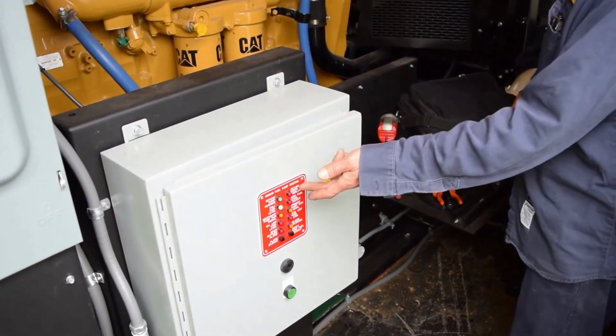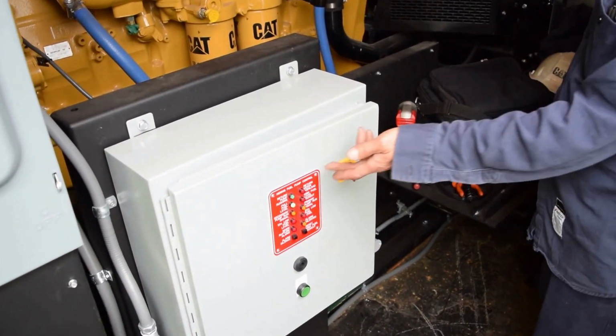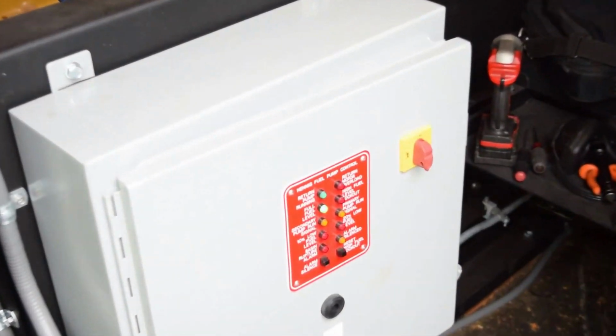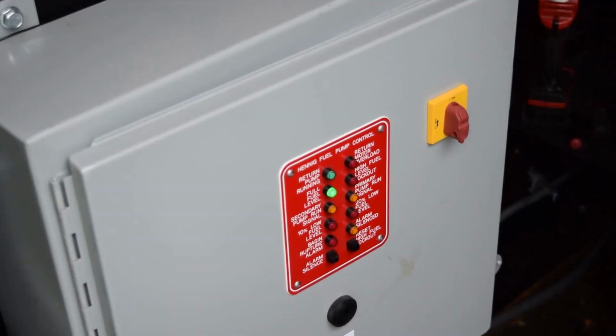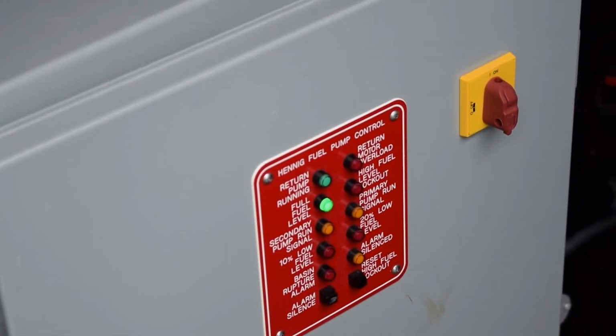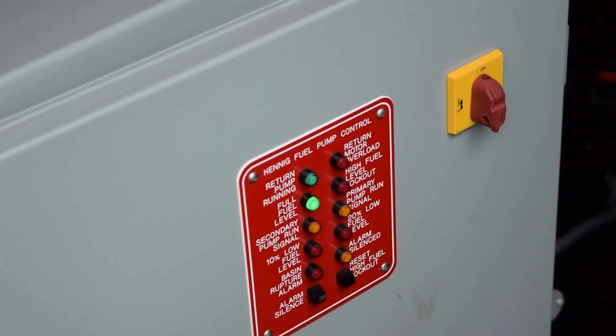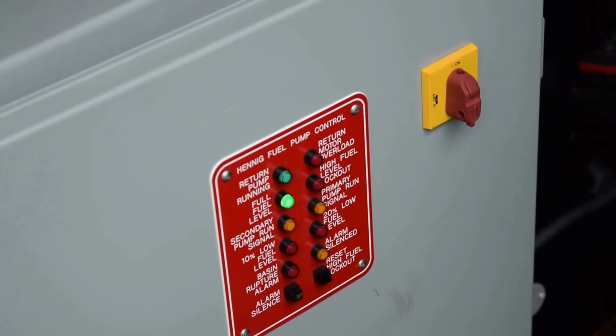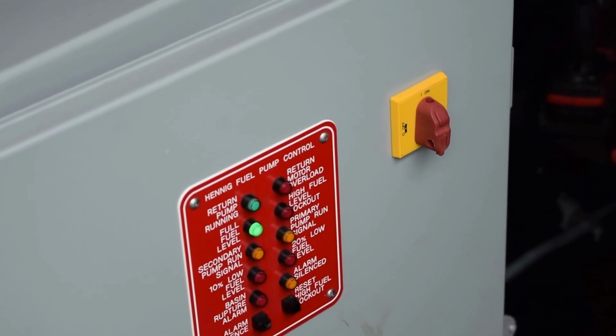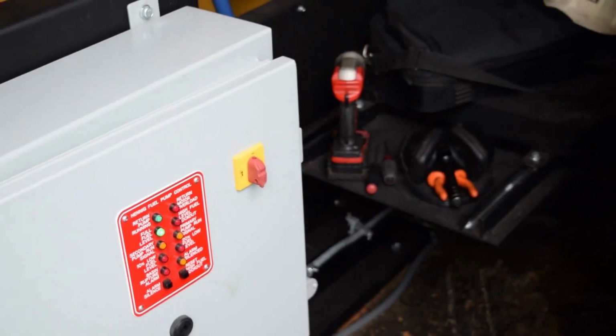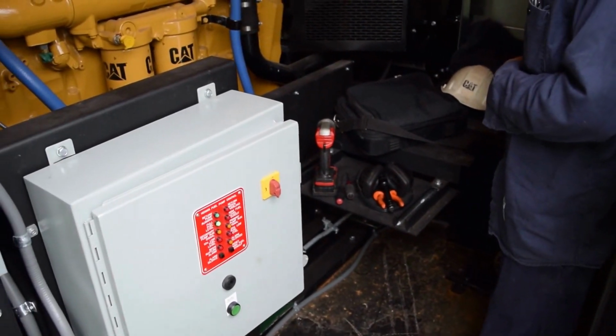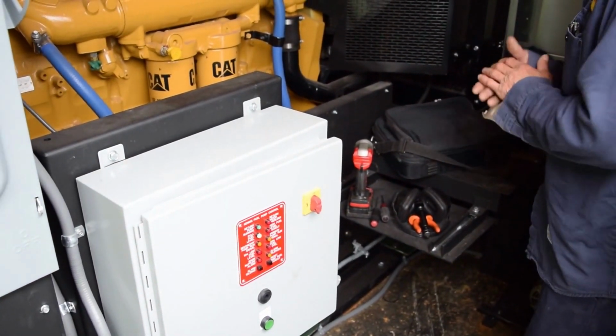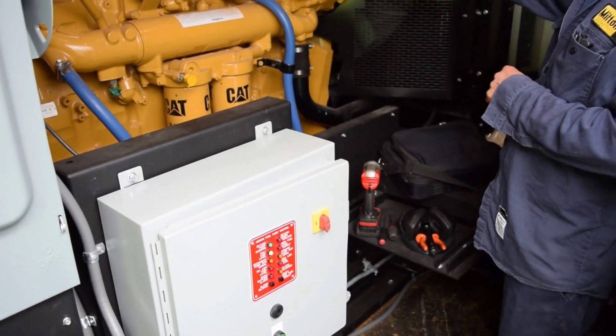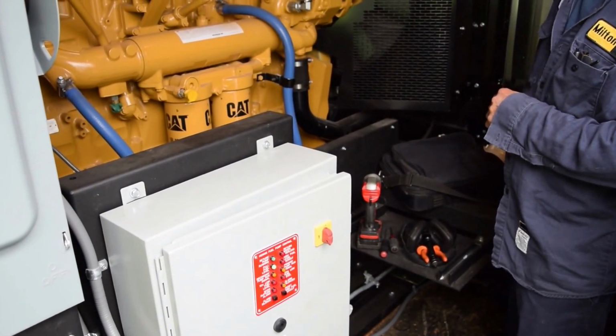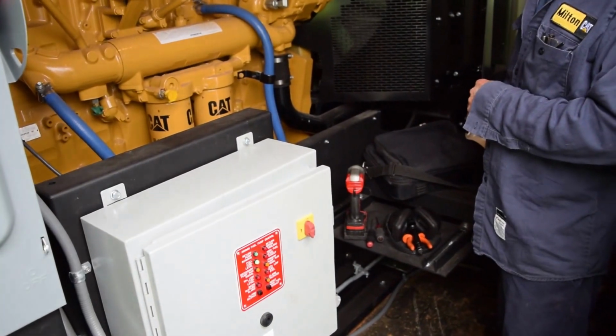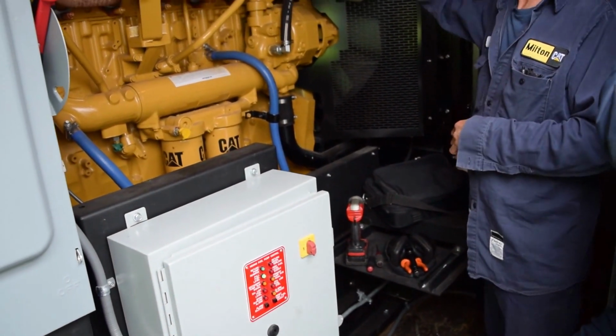And if the fuel level gets that high and it locks out, the red light will come on, and you have to hit the button in order to reset it. So once again, like any annunciator or any other panel that you have, red lights are bad, ambers are telling you a condition, green lights are good. And the return pump is right here, and all of the flow controls are off to the right of me. And there is a manual gauge out on that corner external on the gen set where the emergency vent is that shows you the physical level.